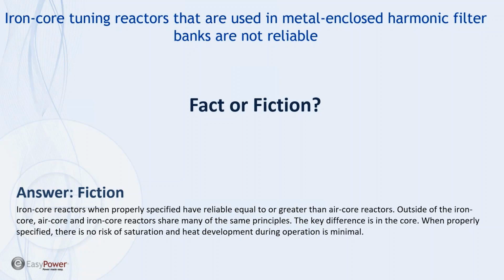The key to ensuring that an iron core filter reactor is reliable is to make sure you specify it correctly. NEPSI takes a position that the fundamental current rating of the filter should be multiplied by 1.35 to 1.5. There should be a significant margin at the fundamental. And then the harmonic current rating should not be based on just the study, but also on having a significant margin between what your study has determined to be the harmonic current and what the rating of the reactor is going to be set at. And I'll give an example.